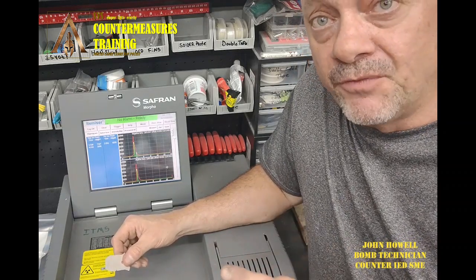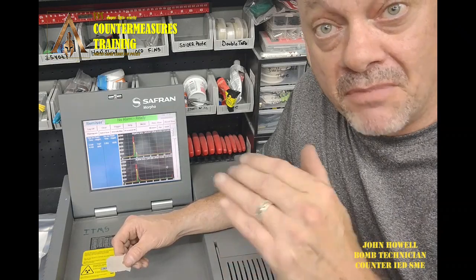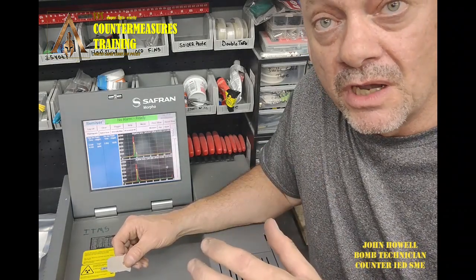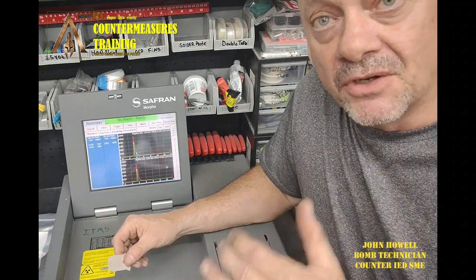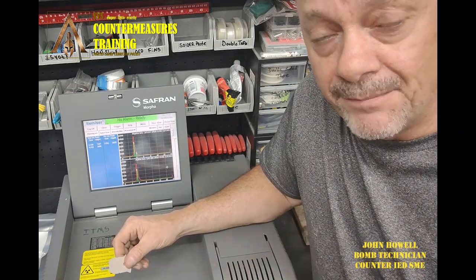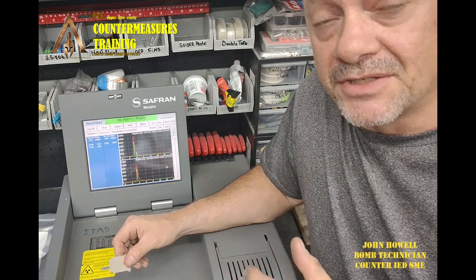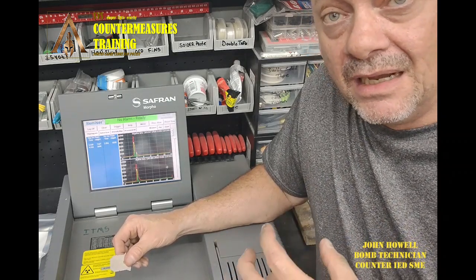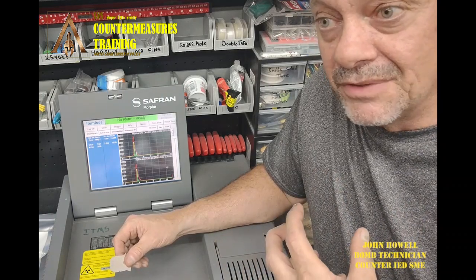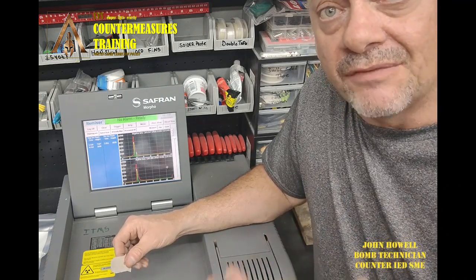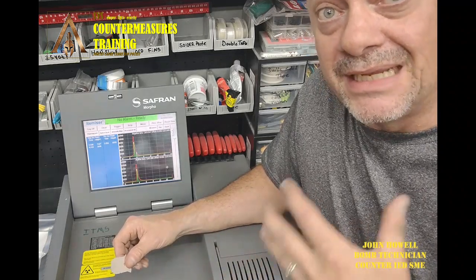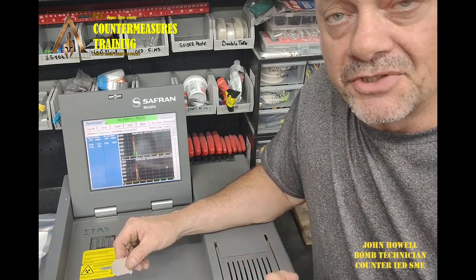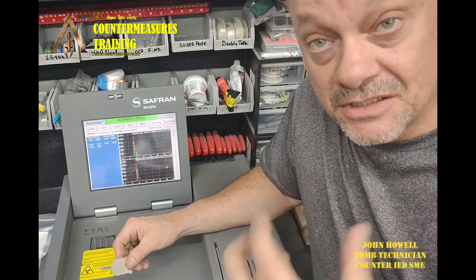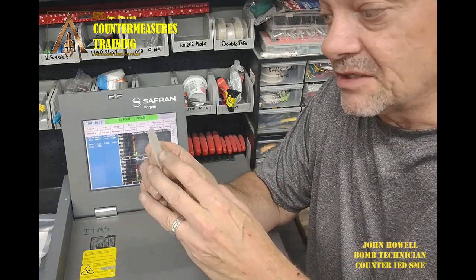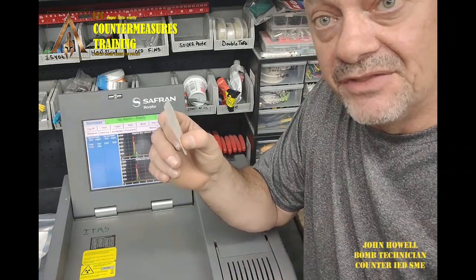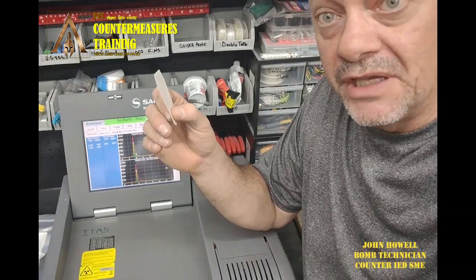So if you're looking for narcotics, you're going to run at a much higher temperature than if you're looking for explosives, because narcotics are a lot harder to turn into a vapor, so they have to operate at a much higher temperature. So when you start looking at a chemical, whether it's a drug or an explosive, you have to look at its melting point and boiling point to get an idea of what temperatures you have to be at to get it to desorb whatever particles you collected on here, to get turned into a gas and then sucked into the system through the desorber.